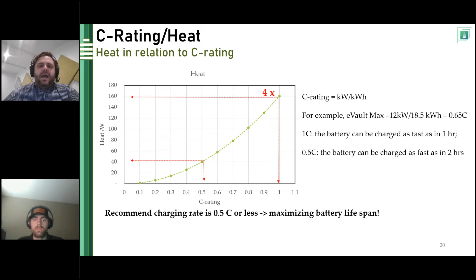Finally, there are impacts on depth of discharge with lithium iron phosphate batteries, just like there are with lead acid. Now, what I like to say is all the technical specifications relevant to the lead acid industry have been compressed when it comes to lithium iron phosphate. Lead acid is really a 6-hour or 10-hour or 20-hour discharge rate battery. They even rate them at 100 hours. Lithium iron phosphate is generally rated at a 2-hour discharge rate, sometimes a 1-hour discharge rate. So our scale has been compressed a bit.